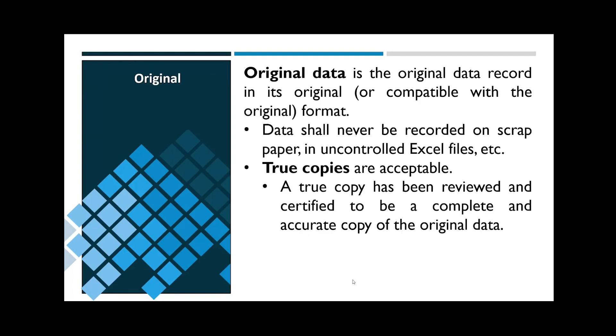Original data is the data record in its original or compatible-with-the-original format. It cannot be recorded on scrap paper or in uncontrolled Excel files, for example. Instead, CGMP data must be recorded in controlled Excel sheets, paginated notebooks, controlled electronic workbooks — anything that has an audit trail and doesn't allow for data to be deleted without documentation and retention of the original data value. True copies are also acceptable as original data. True copies have been reviewed and certified to be a complete and accurate copy of the original data, usually by quality.